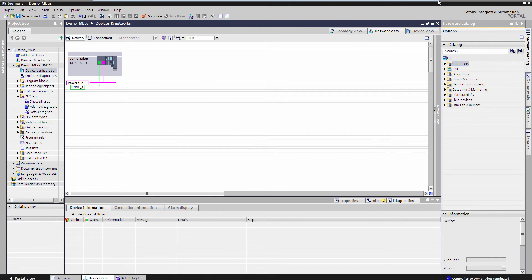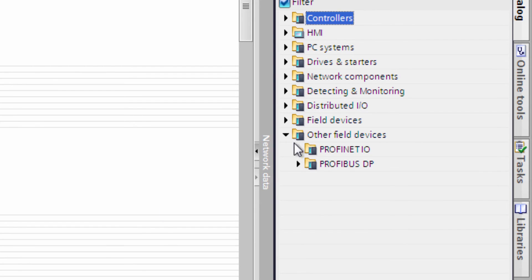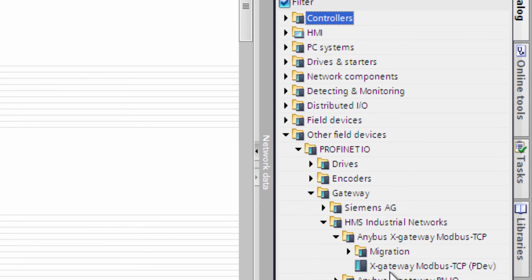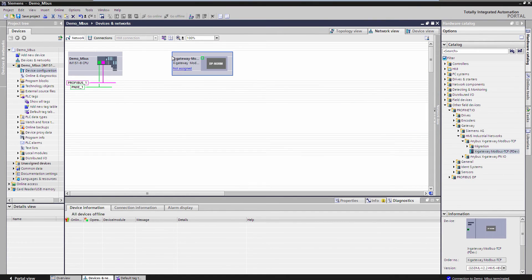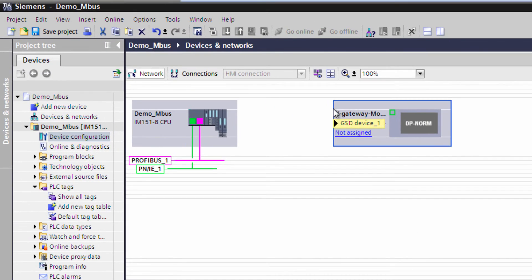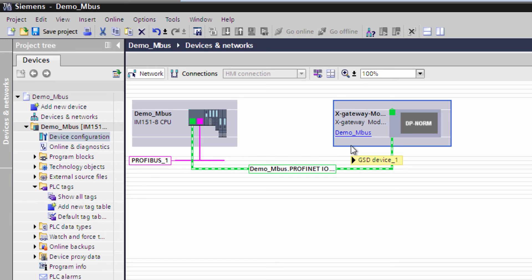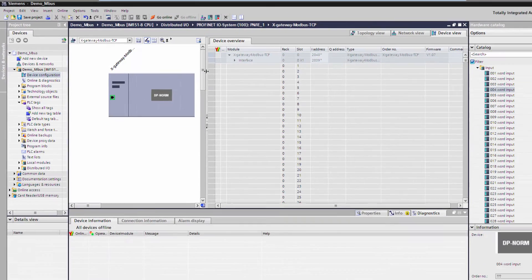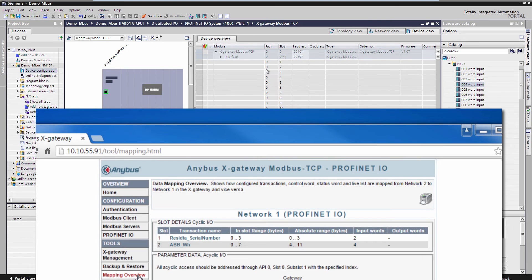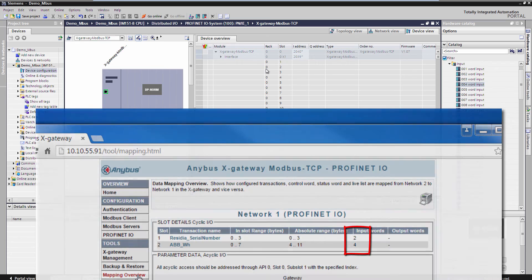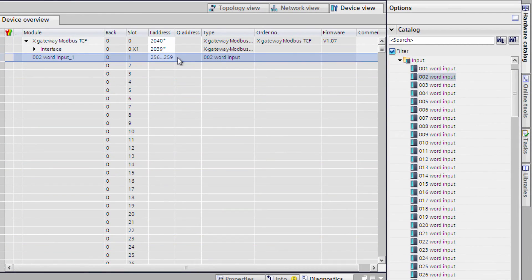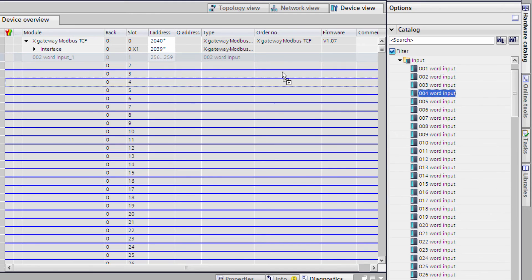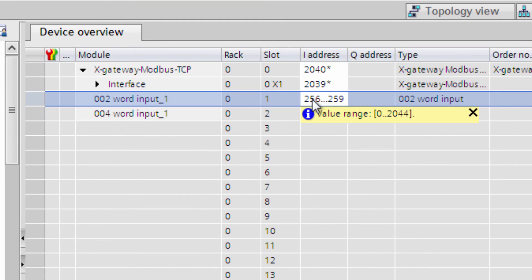To add the MBUS x-gateway modbus.tcp to TIA Portal, I have already added the GSD file which I have downloaded from anybus.com. I browse my way to the x-gateway modbus.tcp and drag it into my configuration. I also assign which PLC system it belongs to, my PROFINET interface in this case. I double click on the unit and also add the modules which we also saw in the x-gateway. As you remember, we could see this in the mapping overview of the x-gateway. This was 2 and 4.